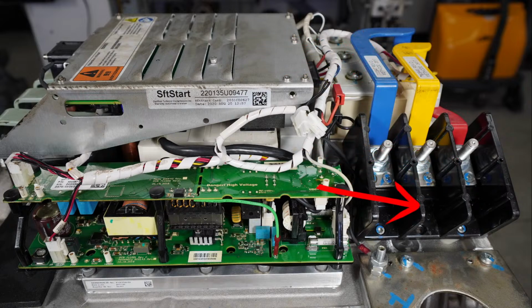And don't just replace the fuses. Don't just reset the breaker and turn it back on, please. If you do have a trip like that, go through these SCRs and make sure that they are good, because you may have gotten fortunate and tripping off once just protected the machine from actually completely self-destructing. But I've seen it where, instead of taking the time to test anything, they'll just go in and reset the breaker, or throw a new set of fuses in and let it rip.